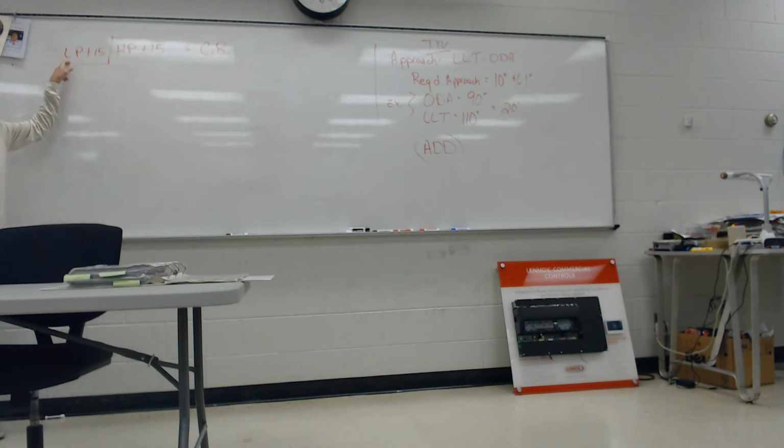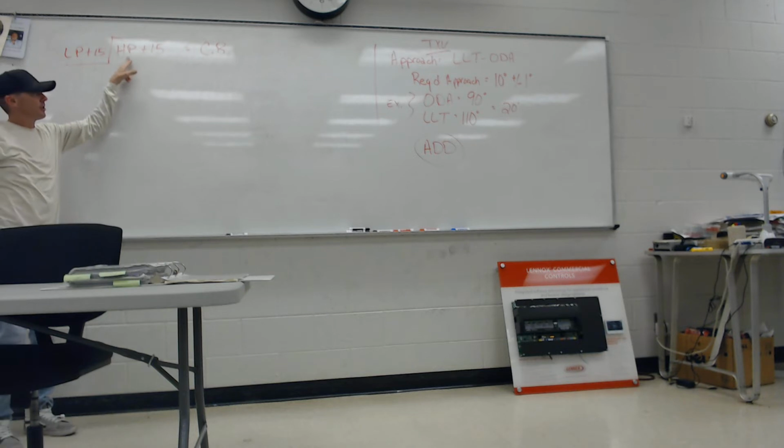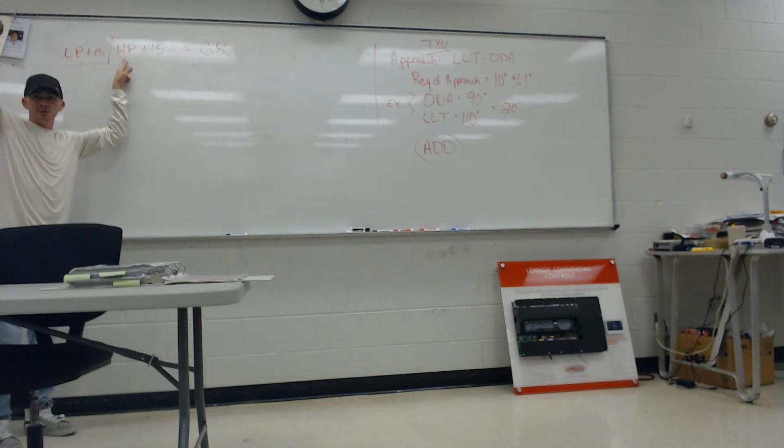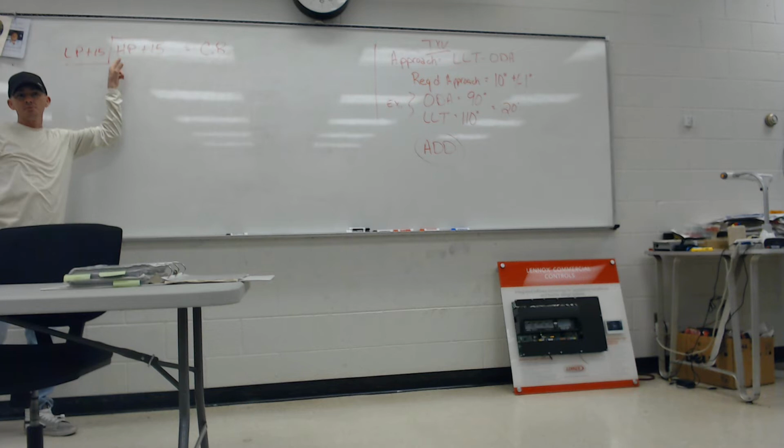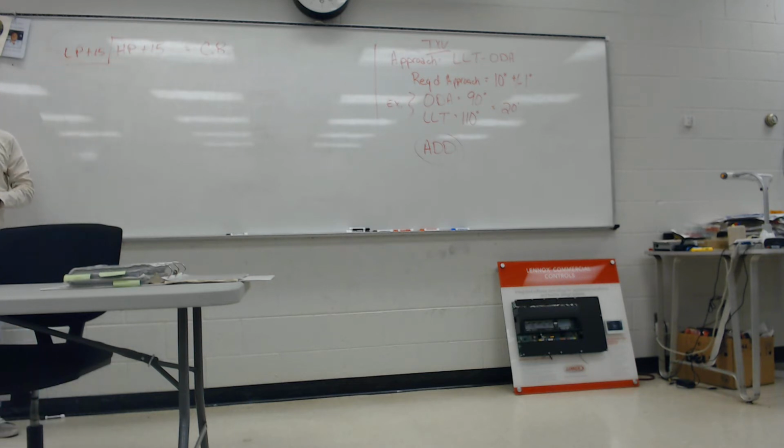But which one will affect your compression ratio more? It's always the suction pressure. Mathematically, if your suction pressure drops 10 psi, compression ratio starts going up. Whereas if your head pressure goes up 10 psi, it won't affect it near as much as that suction pressure did. So suction pressure really affects compression ratio. We good? Mm-hmm.